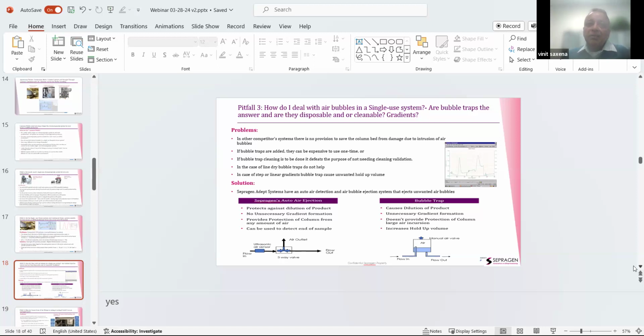And I don't know if you can see in this little chart that we put up, in this chromatogram, on the left is a peak without any bubble trap, and on the right is what you get if you have material going through a bubble trap. Because you have a mixing of two fronts between different buffer changes, they're not sharp. Cleaning validation is an issue if you wanted to reuse, loss of materials, and certainly large holdup volumes.